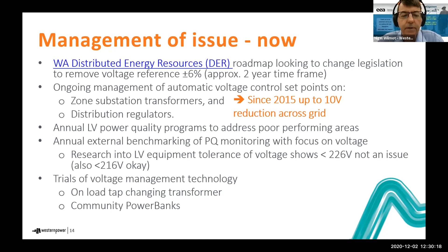We also have trials of management technology. We've got 13 on-load tap changing transformers at the LV level being trialled at the moment, dealing with the issue at the source, and also utilising 14 community power banks at the moment, and looking at deploying up to another 100 of those community power banks to address reverse power at the micro level. These are about 100 kVA, 400 kilowatt hour community power banks. Since 2015, we have a 10 volt reduction across our grid.